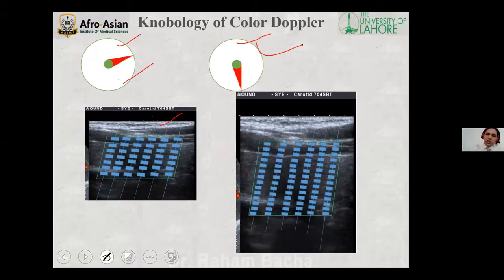So you can see that this image takes more time as compared to the first one. So with the increase in color box depth, the time required for the completion of one image on the ultrasound display will be greater than for a shallow color box. And this way, it will deteriorate temporal resolution. It will reduce frame rate, and frame rate eventually results in the deterioration of temporal resolution.